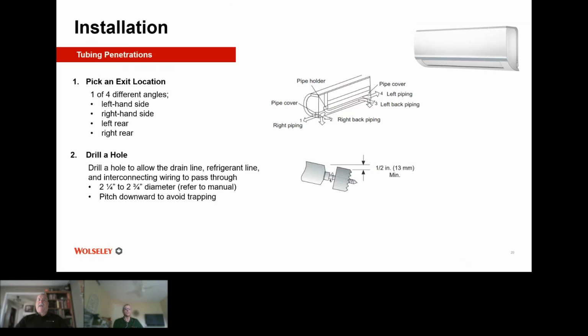Now, as Joey was talking about before, with installations, it's critical that you know the brand and know the clearances and the limitations that it has on installation. So, for example, with this high wall unit, I want everybody to know that there are 4 possible exit locations that you can do for condensate and line set on your high wall head unit. You can do a left-hand side exit location. You can do a right-hand side exit location. You can do a left-hand out of the rear, so you will not see it come out the side of the unit at all. And then you can do a right rear exit location.